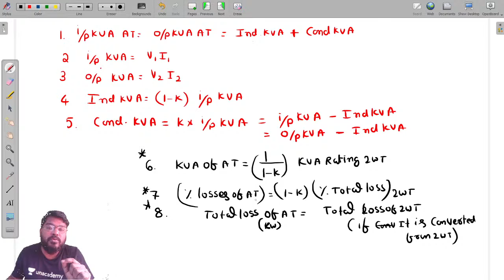Next, another formula: percentage impedance of the auto transformer is equal to 1 minus k times of the percentage impedance of the two winding transformer.